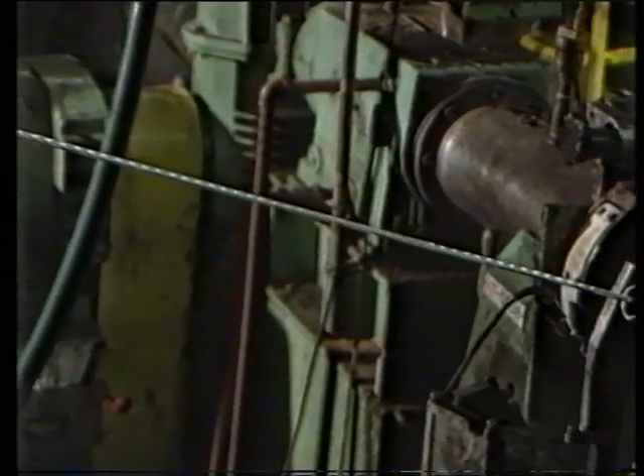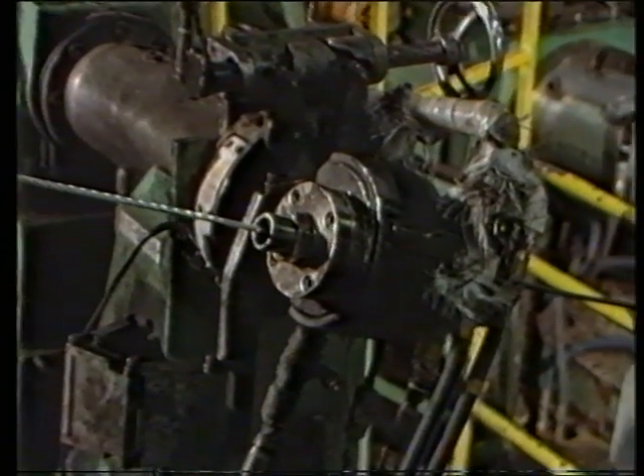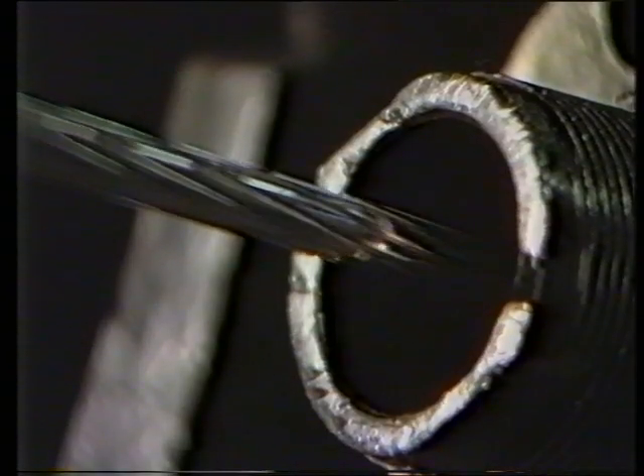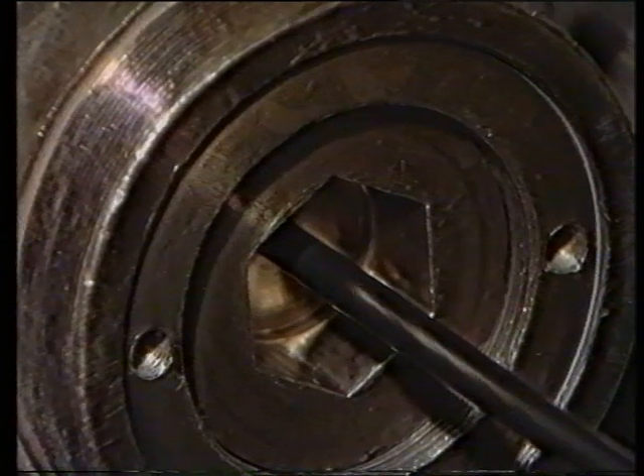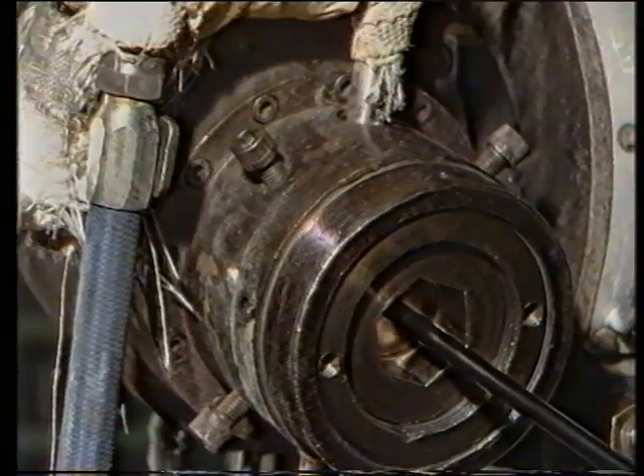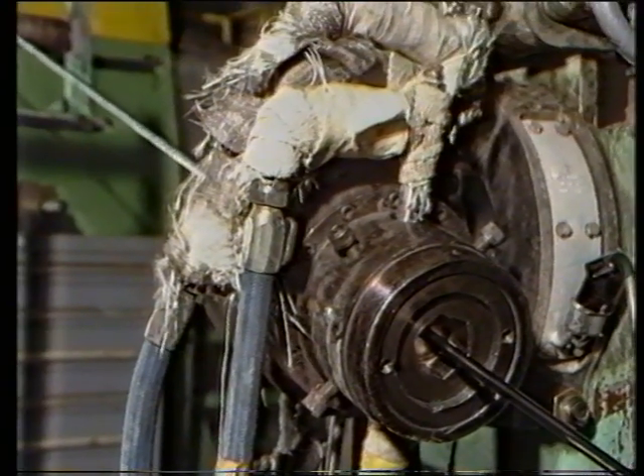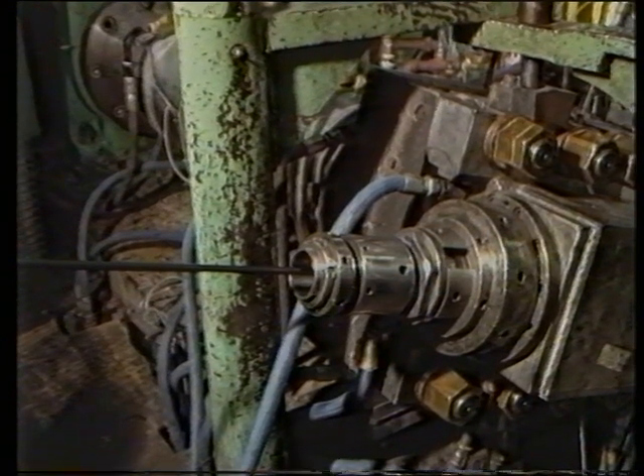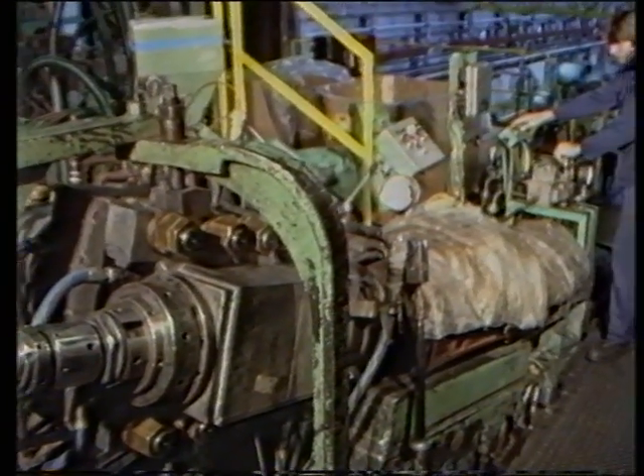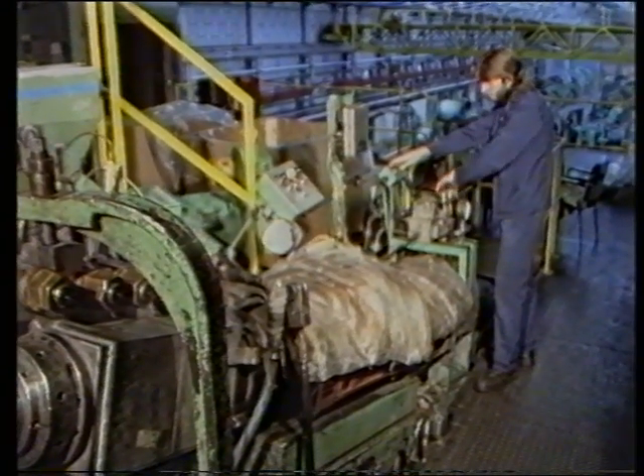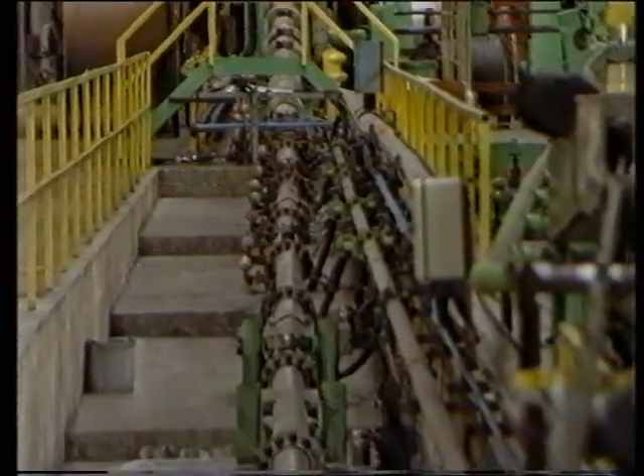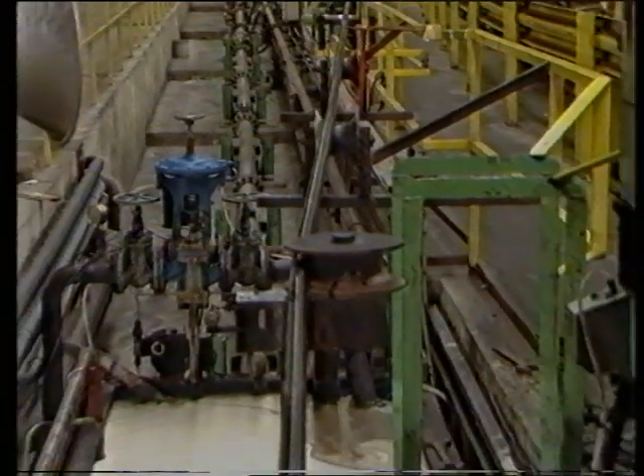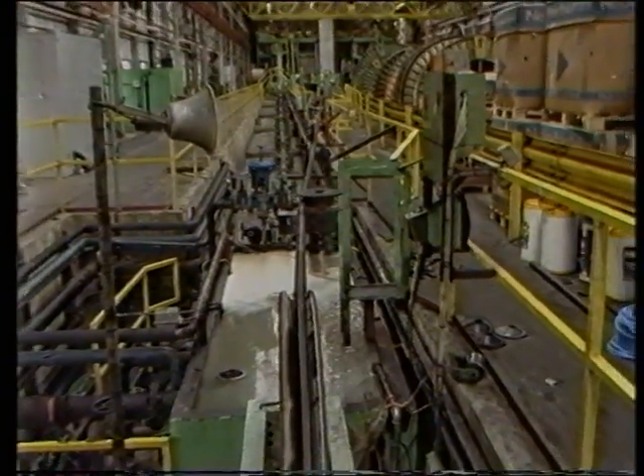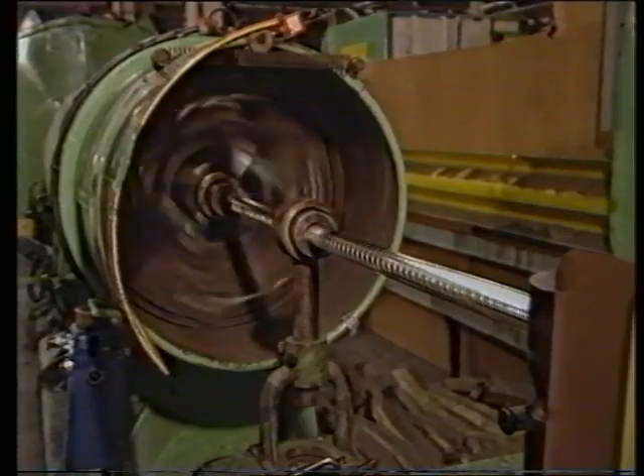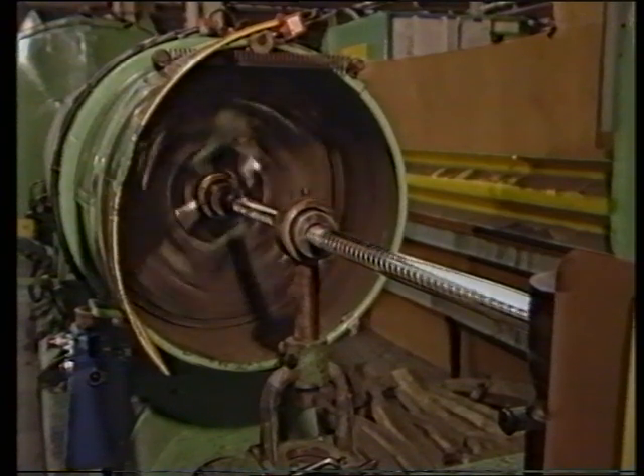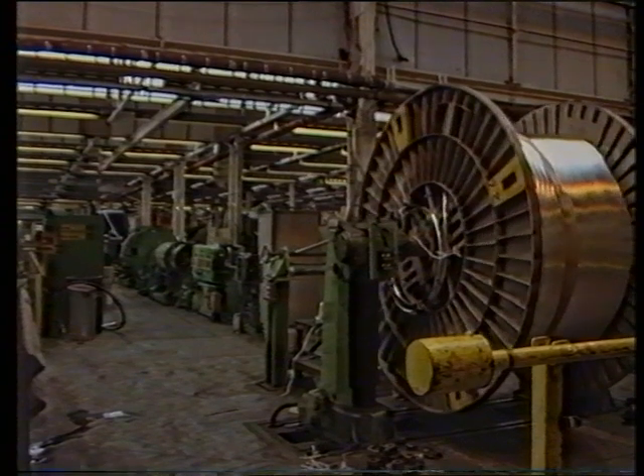Each conductor is subjected to a triple extrusion process where it's screened, insulated and vulcanized in one operation. First, the conductor screen is applied to reduce unwanted electrical discharges. Then, the water-resistant ethylene-propylene rubber insulation, specially developed by Pirelli for use in the manufacture of submarine cables, is extruded around the conductor. Finally, the insulated core passes through a long catenary tube where it's vulcanized at very high temperatures. A metallic screen of tin copper tape is then applied to the conductor. This is very important as it controls any stress which may occur within the insulation.